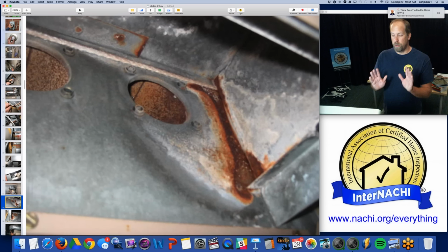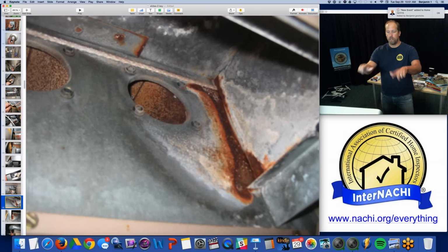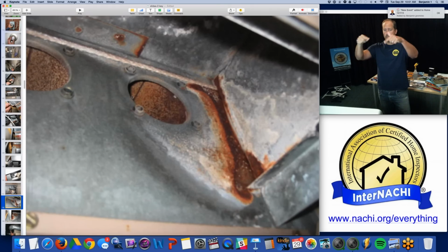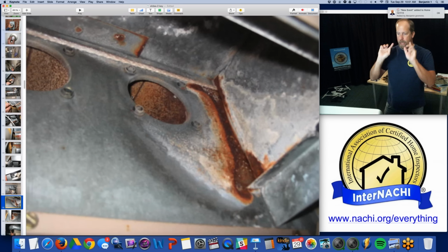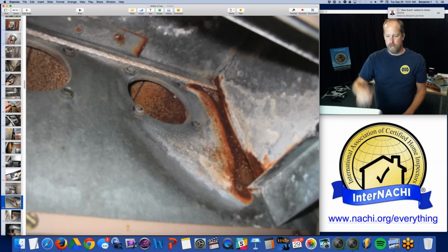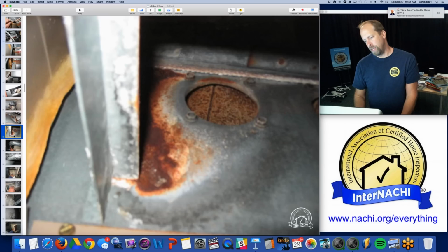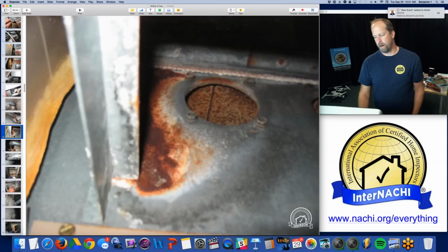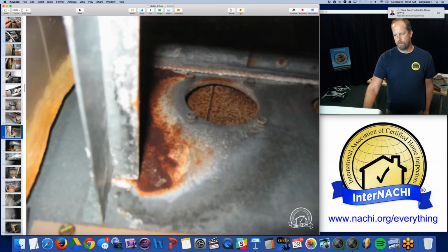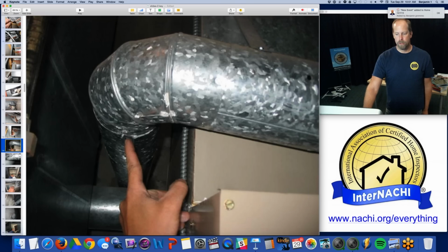And there's the natural draft hood. So there's the heat exchanger, passes through. The burners and ribbons are on the bottom. Hot exhaust gases pass through the heat exchanger, serpentine up, come out the top, and then they draft up naturally with the flue pipe into the chimney stack. And you can see there's a lot of stuff going on here. Could be a dangerous situation, or maybe there was.